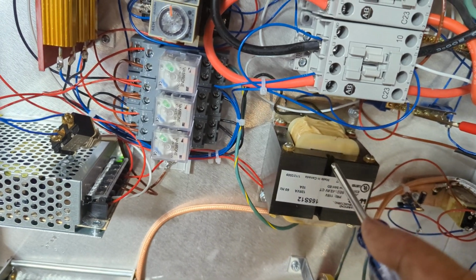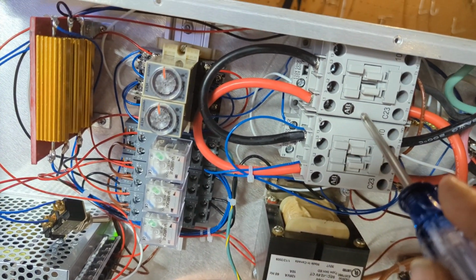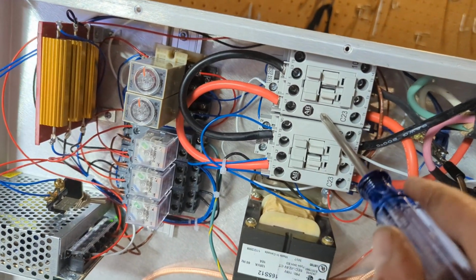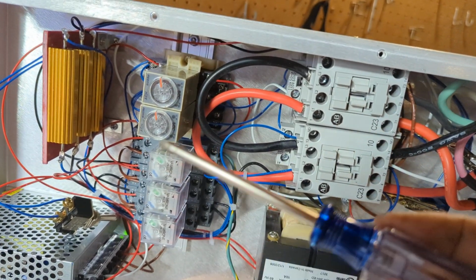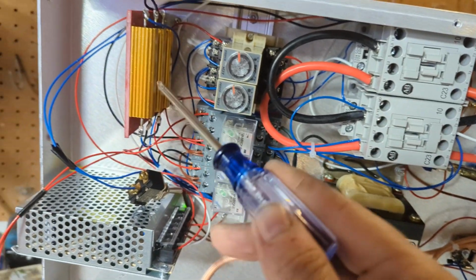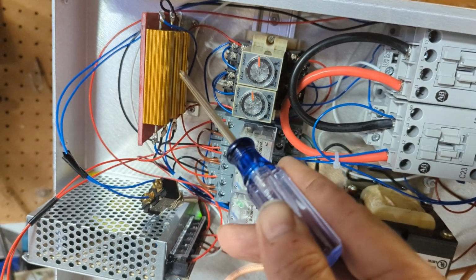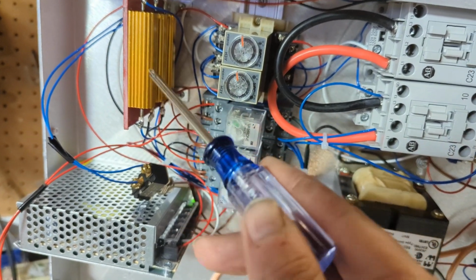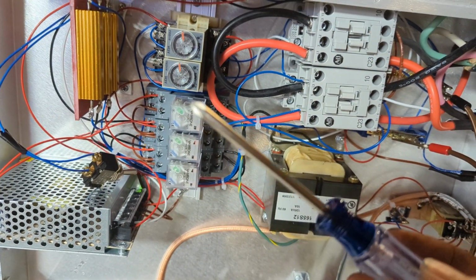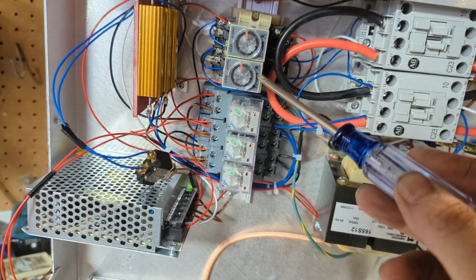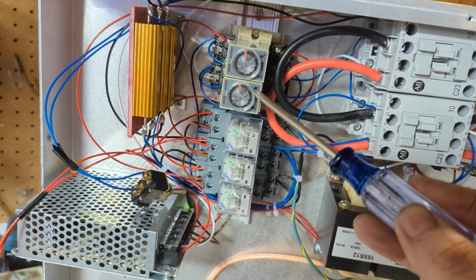At that same time, it also engages this first Allen Bradley, which allows the high voltage to slowly start rising, utilizing the 100 ohm resistor, which is all by itself right here. It's charging that capacitor bank, and it's doing that until this timer expires.